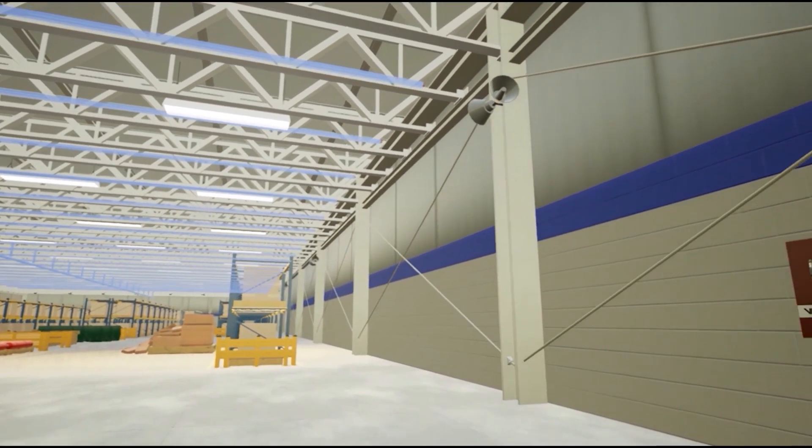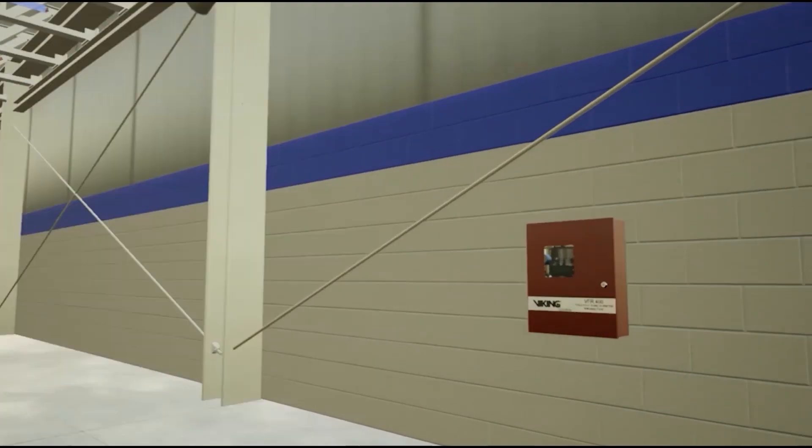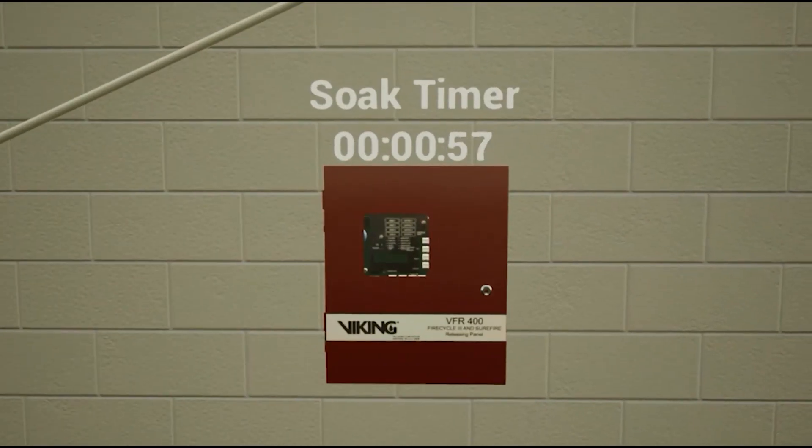The heat detector resets. The soak timer is now initiated. The soak timer is programmable. Water will continue to discharge from the sprinkler for the specified amount of time. The soak timer can be programmed between 30 seconds to 30 minutes.